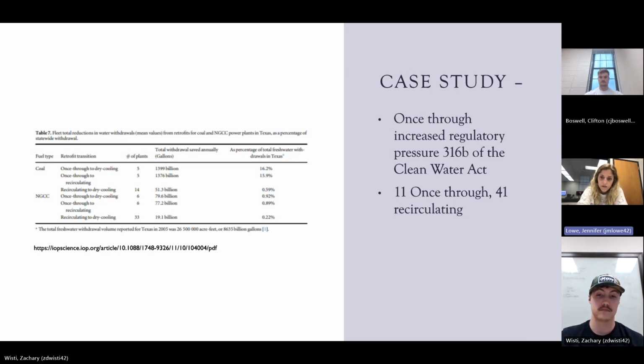There's a case study based in Texas where they retrofitted existing coal and natural gas power plants with alternative cooling systems, either recirculating or dry cooling. Using an assessment tool, they estimated annual reductions in water and cost per gallon of water saved. Retrofitting all coal plants with dry cooling systems resulted in a substantial reduction in water withdrawals at a cost of roughly 68 cents per gallon of water saved. These reductions in water withdrawals that result from retrofitting the cooling systems at the NGCC plants are smaller but significant nonetheless. Retrofitting to dry cooling systems achieves significantly more water savings per monetary investment than recirculating systems making the same transition.